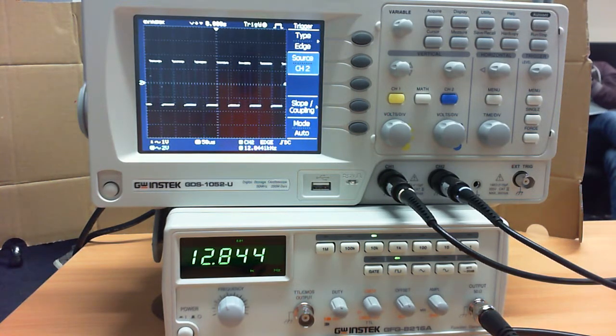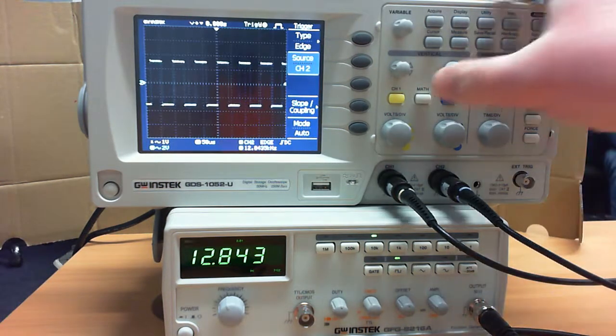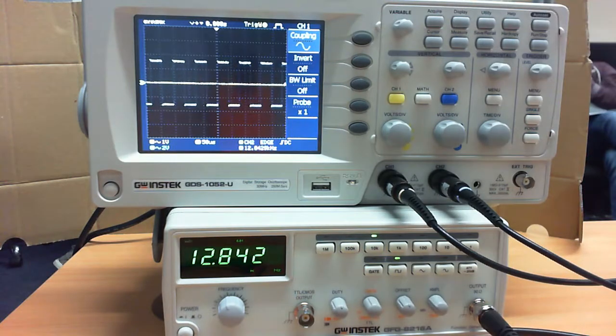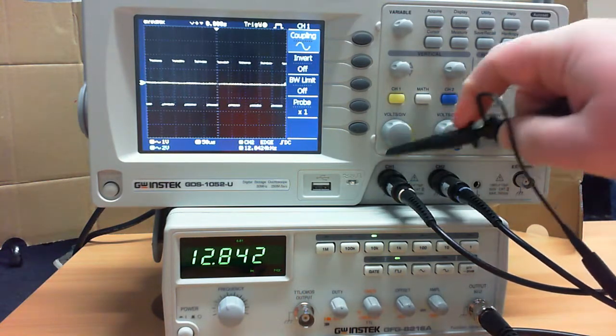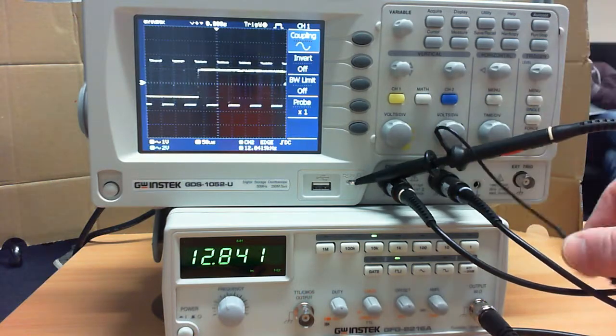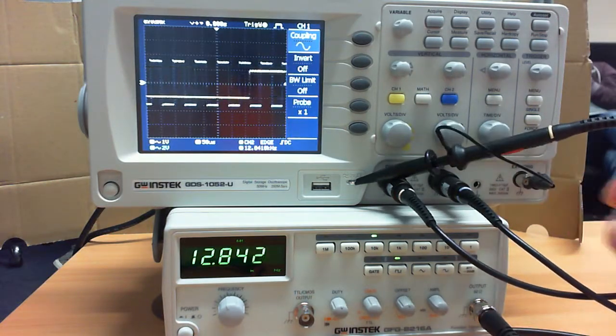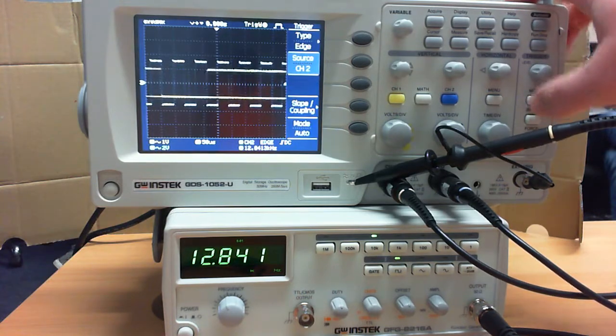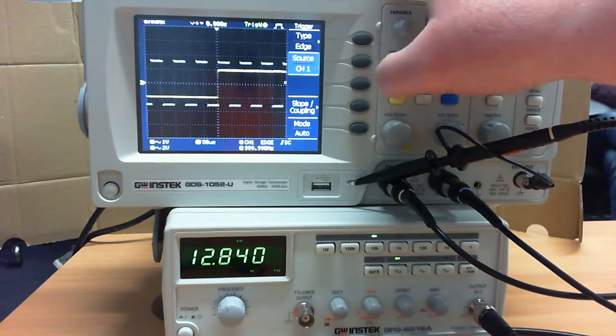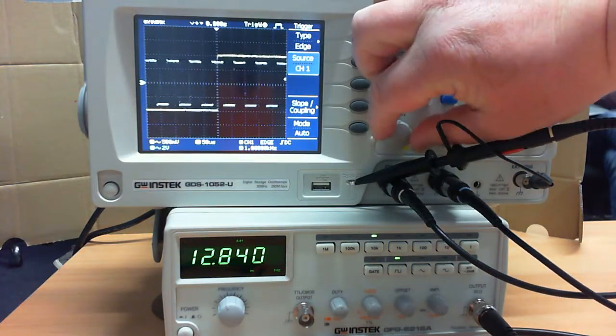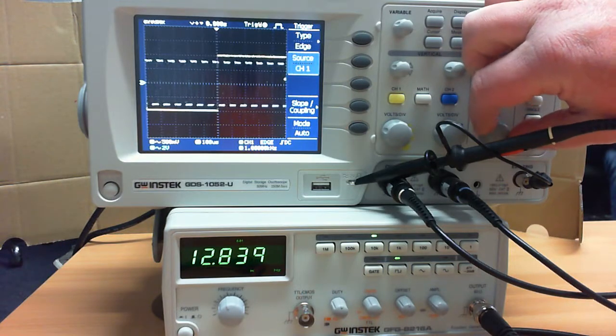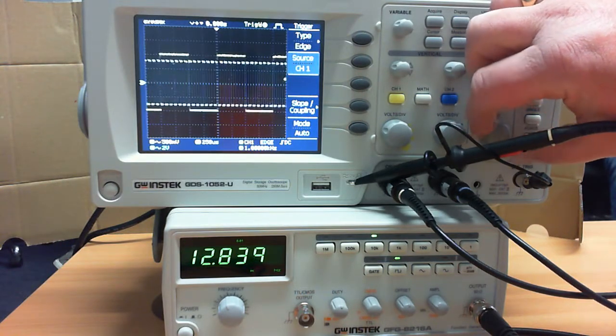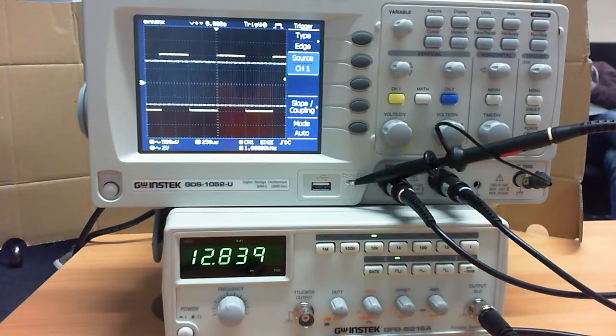What I said we were going to do is take the calibration signal from channel 1 and match it on channel 2. I want the two signals on the screen at the same time. So on channel 1, I need to hook my probe back up to the test signal and my ground. I'm going to trigger off channel 1 for a minute. I'm going to bring my signal in. I want two peaks, two troughs. Okay, so the yellow one is my calibration signal.